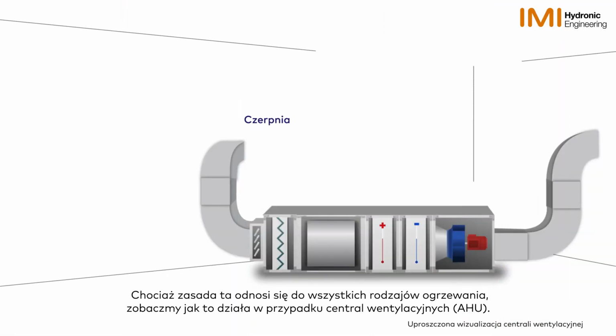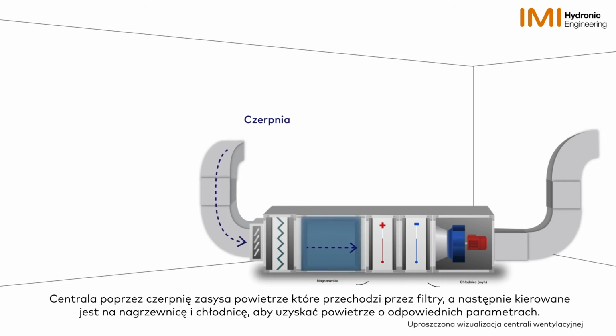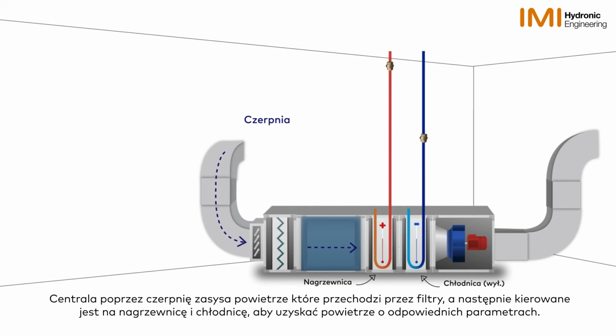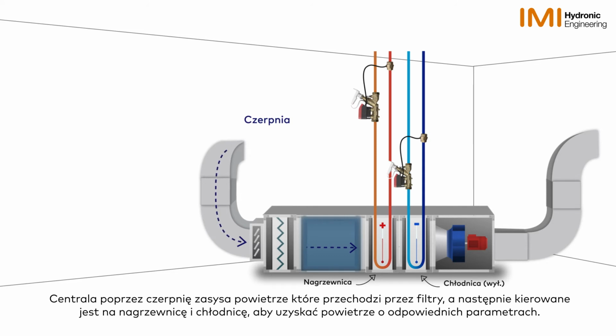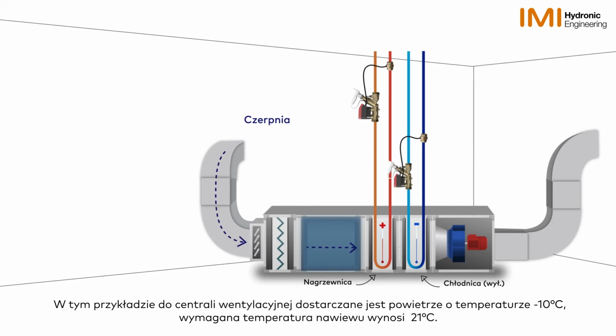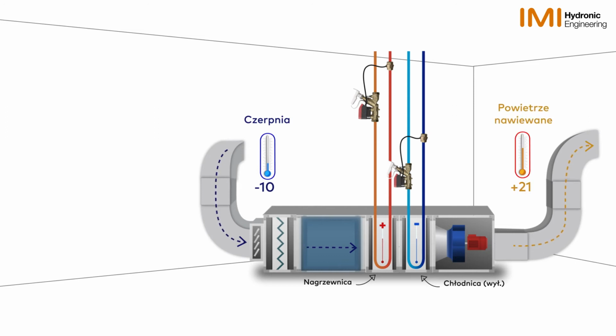Although this principle applies to all heating types, let's see how this works for an air handling unit. The unit has an air intake which draws air through the filters, over the heating and cooling coil, and then emits air at the desired temperature. In this example, the AHU is designed to manage an intake temperature of -10 degrees C and achieve an output air temperature of 21 degrees C.